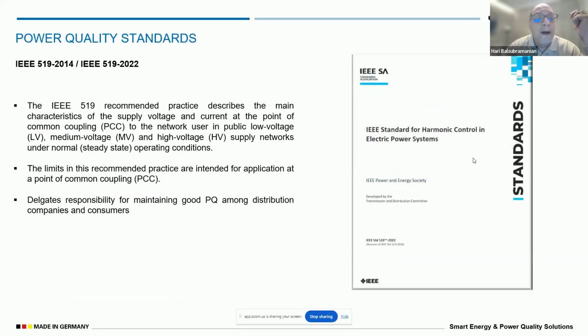It talks about IEEE 519 actually. When it comes to it, it talks about different kinds of practices, which clearly demarcates who is responsible for what. The voltage harmonic is the responsibility of the distribution companies, and the current harmonics, because the loads generate current harmonics, are the responsibility of the consumers. So it very clearly demarcates this, and it goes to all the voltage levels.